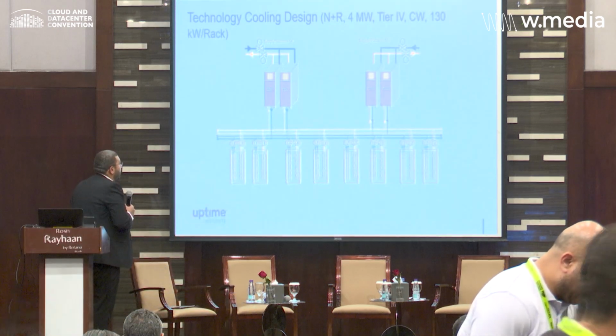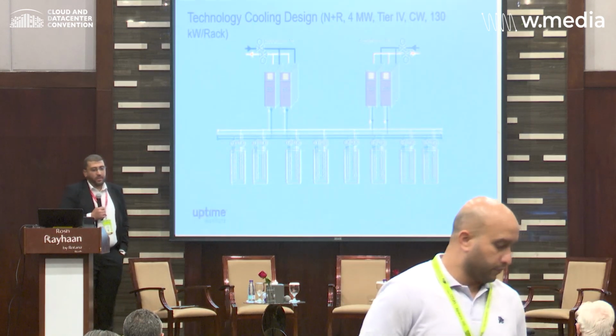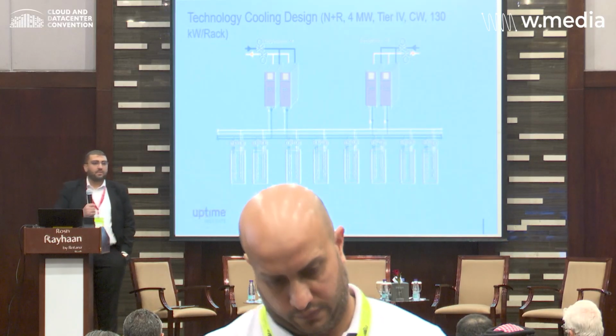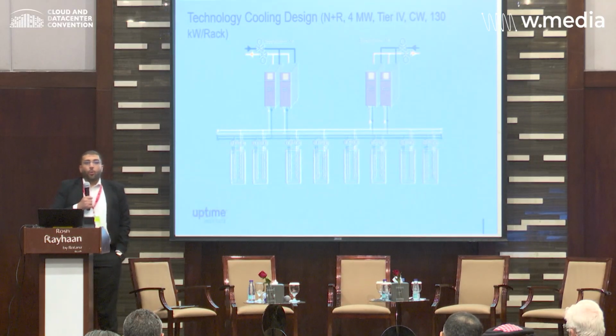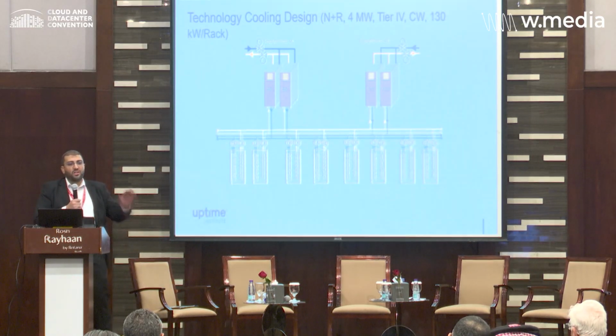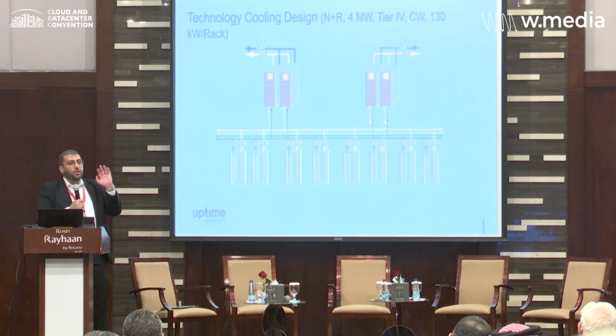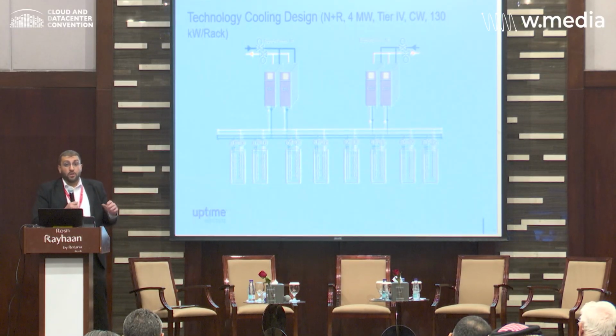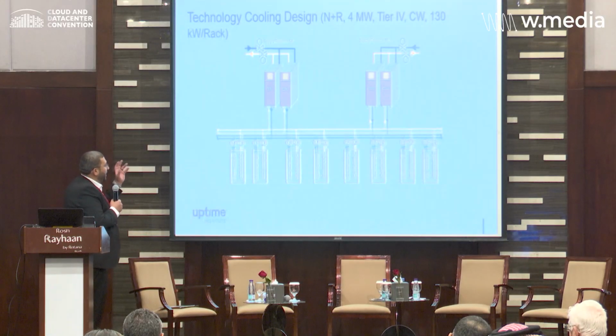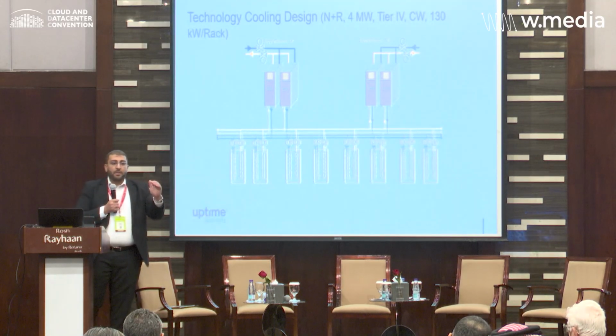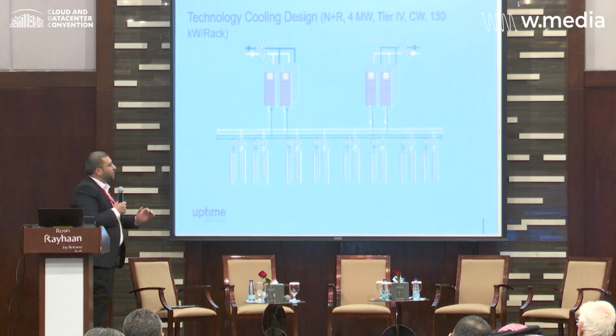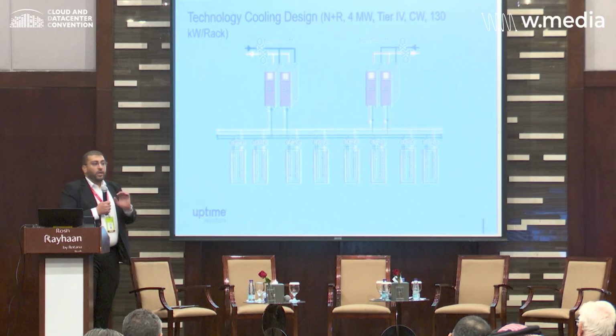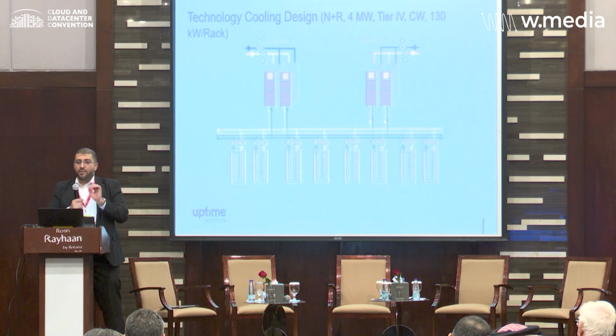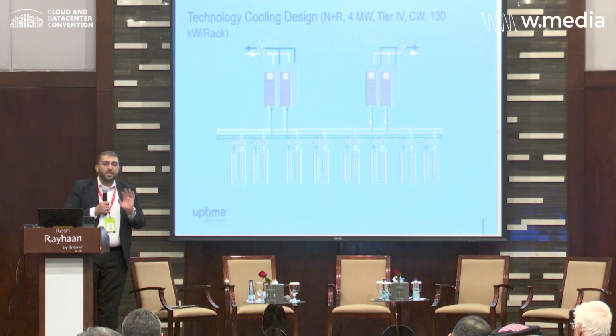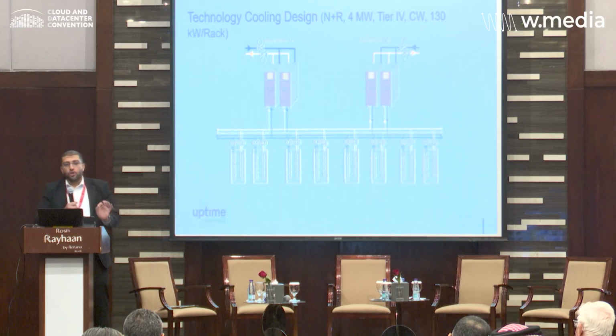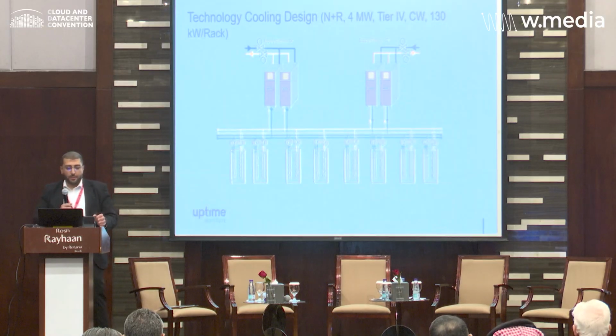Another configuration is N plus N. Again, in Uptime, our tier topology is performance based. That means you can achieve the tier level in multiple ways, with multiple designs. There is no one straightforward design. It's a performance outcome. So another way of achieving Tier 4 is to have an N plus N configuration with separate and independent headers. In case you have a leak in any of the headers, it will act independently. The leak will be isolated automatically, and there will be no impact on your AI workload. Your AI workload will keep running as normal.